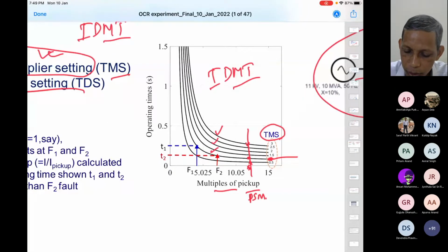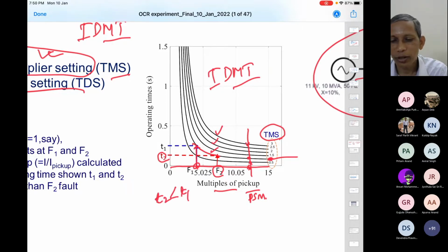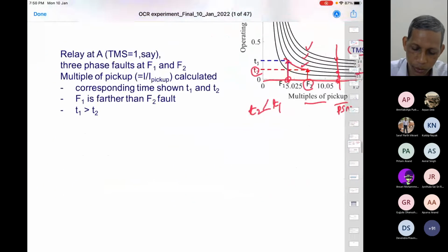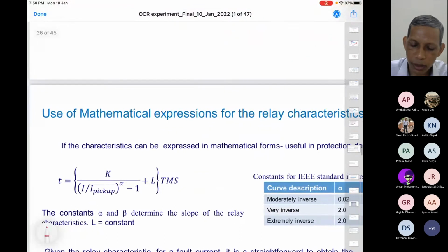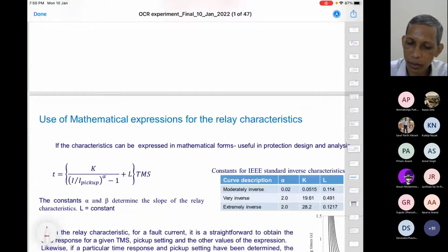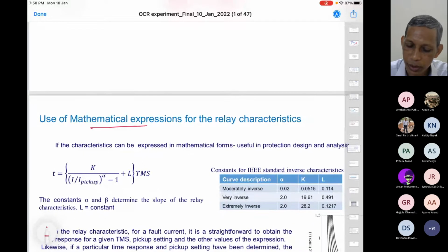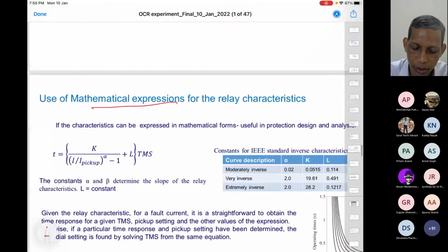Now let us see what will happen here. On the x-axis, any curve we see, let us say I'm talking about the T1 curve. F2 fault current is higher, so that's why this PSM will be higher. So the time T2 is small, and for F1 the corresponding current is small, so T1 is higher. So you see here T2 is less than T1. If you take any curve and use it, the corresponding time information is obtained purposefully. We'll see the application perspective. These curves can be expressed in terms of mathematical expressions which the IEEE has defined, and the mathematical expression for this is this.